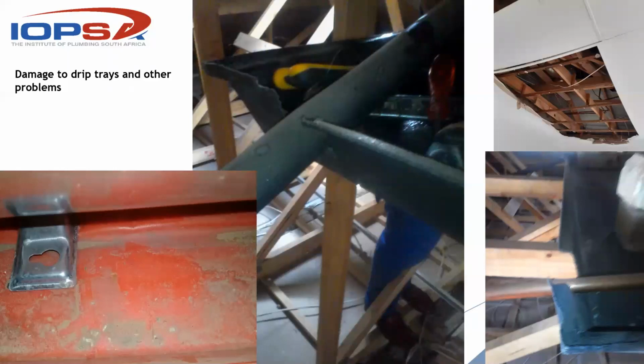So the risk factor is high that the tray could become damaged, especially when you don't get the timber supports underneath the tray corresponding nicely to that foot. We've seen it in the past where the timber support is slightly off center, and together with that foot, it's almost creating a scissor effect, and it slices through that tray. So that's a bit of a red flag when we see that.